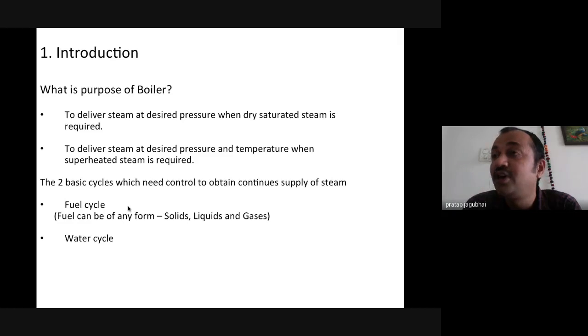Then you can have an economizer. The economizer is a heat recovery device connected to the outlet of the furnace, recovering heat from the flue gas to preheat the water, which is fed again to the boiler through the tank. Air preheater is again a heat recovery device, where the flue gas is utilized to preheat the air which is fed inside the furnace. So these are the terms. Mechanical engineers will be aware of them, and a few electrical engineers will be too. But for the sake of the electronics engineers, I would like to dwell on them, so you can keep in line with the presentation.